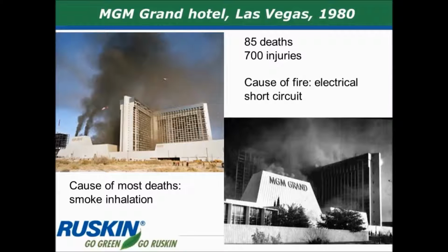Way back in 1980, there was a horrendous fire at the MGM Grand Hotel in Las Vegas. Unfortunately, 85 people died and over 700 were injured. The fire broke out early in the morning on the casino level of the building, and most of the deaths were due to smoke inhalation. A lot of the smoke went up elevator shafts and stairwells, and everything that could go wrong did go wrong. There were some fire dampers in the building that they found out later had blades that had been screwed into the open position and could not close, and on some of them, the fusible link had been replaced with steel wire to hold the damper blades in the permanent open position. It was a terrible event.